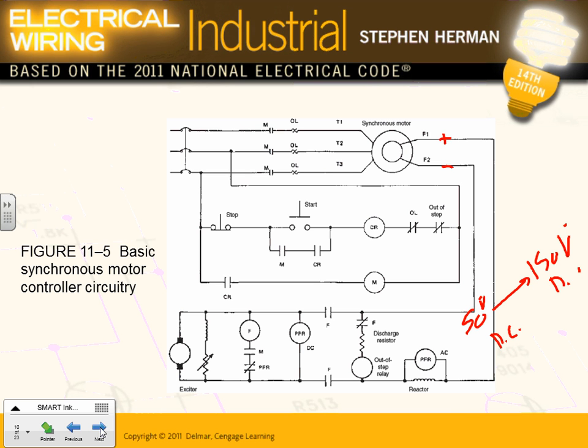And here's your control system for this, without getting into the details. Here's my power factor. They have a bunch of power factor relays. It senses what the power factor is and adjusts the DC to get you this amount of VARs to maintain the power factor at this amount or this amount, because the load fluctuates in your building. So that's your control system for synchronous motors. What do synchronous motors do for a living? They spin the rotor, nothing on it. They get overexcited by putting more DC on the rotor, and then they get you a leading power factor. Any comments, guys? Any questions about this? Overexcite the synchronous motor, get you VARs that you can correct.